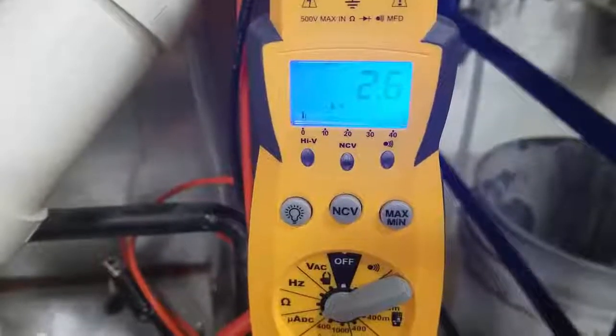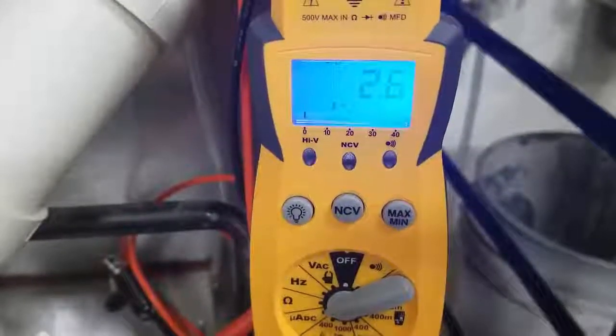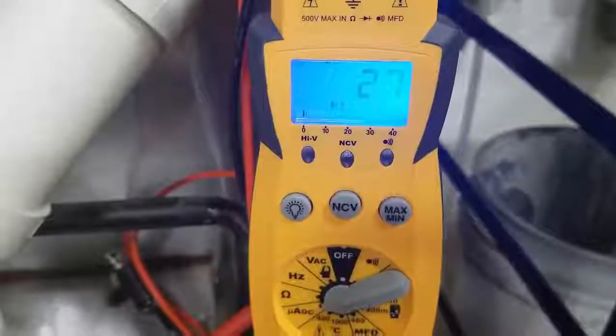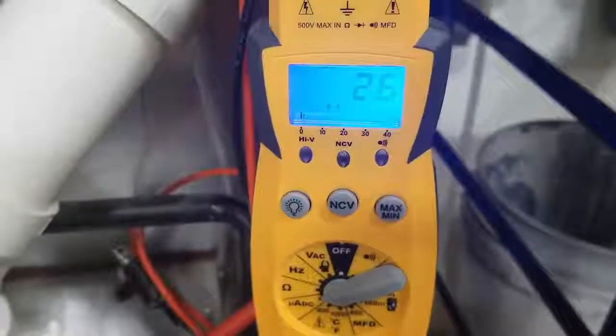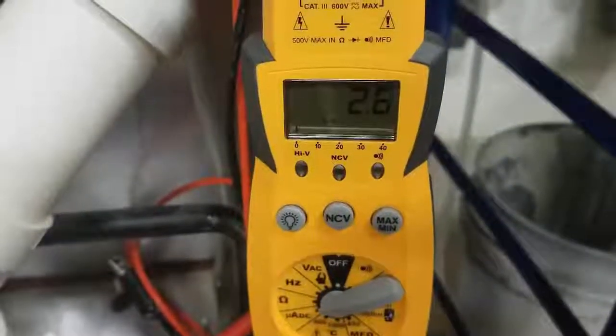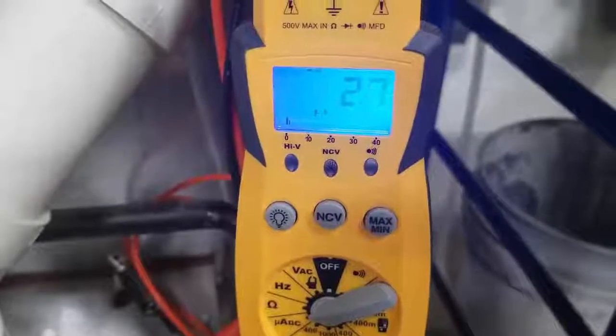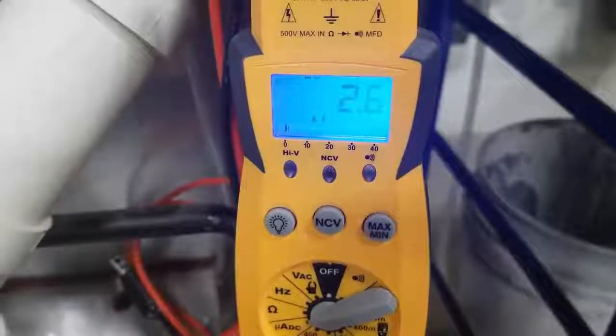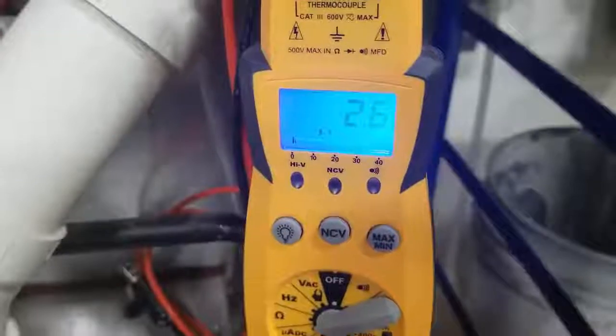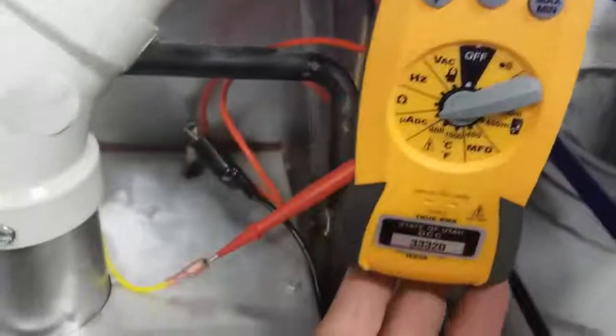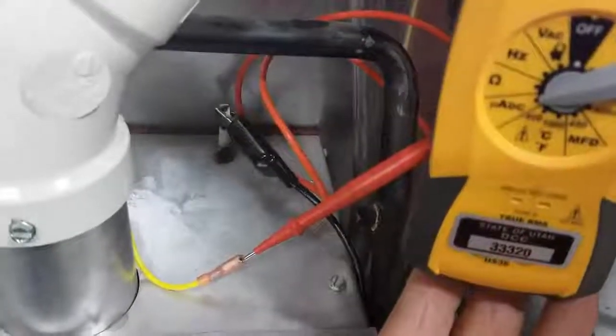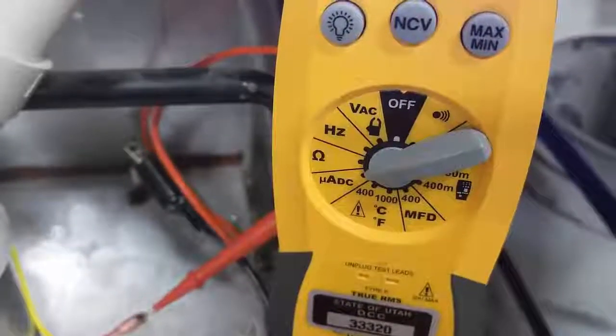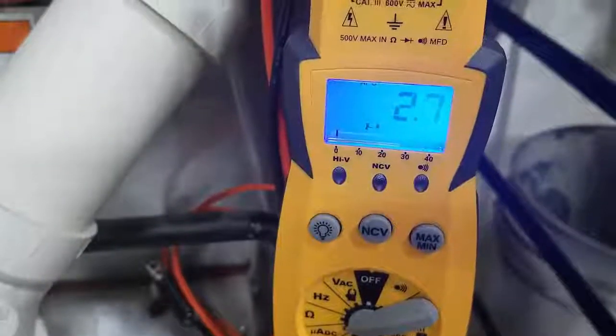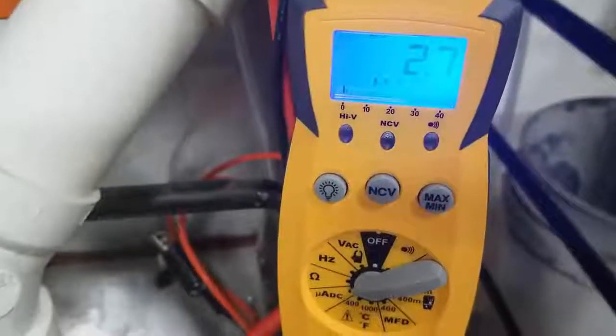Okay, my burner's just fired. Getting a good strong flame signal. Running about 2.5, 2.6 microamps. Typically anything over 1 is good. Get up into 4 and 5, that's really good. If that signal is weak, so 1 or lower, I try cleaning the flame sensor first. If after cleaning it, the signal is still weak, then I'd go ahead and replace the flame sensor. Again, we've just wired the flame sensor in series with our meter, and we're set for microamps DC. Super quick and easy check to make sure we got good flame signal.